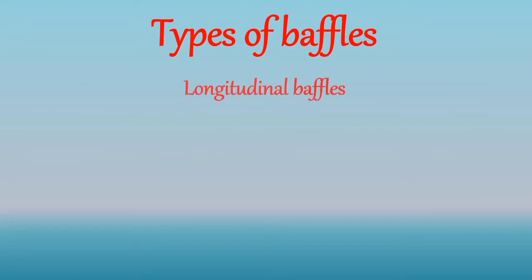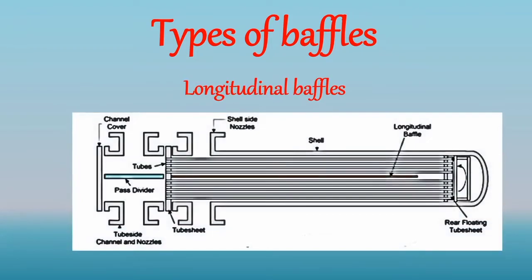So what are longitudinal baffles? These baffles are arranged such that they are parallel to the axis of the shell. They are used to control the overall flow direction of the shell fluid such that a desired overall flow arrangement of the two fluid streams is achieved. That means it acts as a partition for the shell side fluid, and hence the shell side fluid passes through the shell two times.